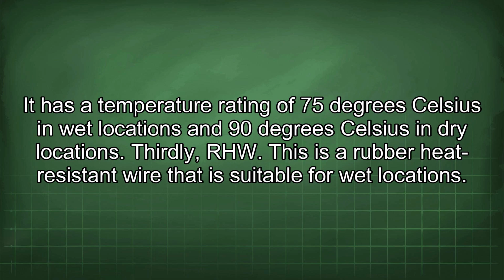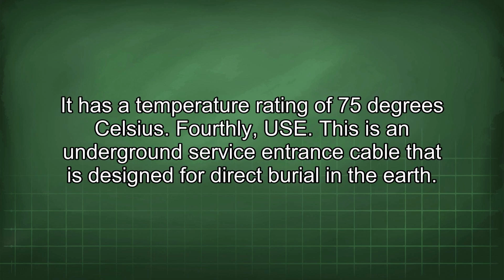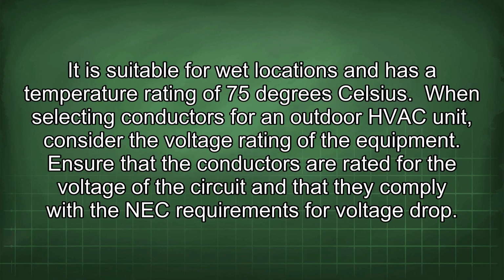Thirdly, RHW. This is a rubber heat-resistant wire that is suitable for wet locations. It has a temperature rating of 75 degrees Celsius. Fourthly, USE. This is an underground service entrance cable that is designed for direct burial in the earth. It is suitable for wet locations and has a temperature rating of 75 degrees Celsius.